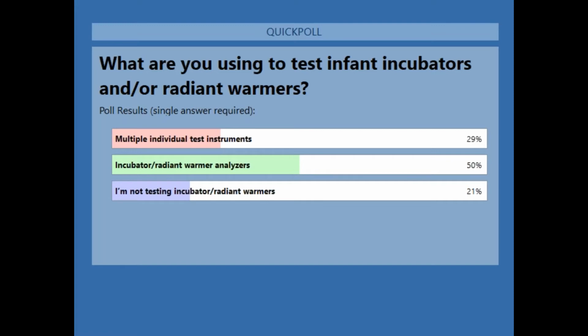Well, first of all, I think this is refreshing, because when we first introduced the original INCU, the number of people using multiple individual test instruments as a percentage of all respondents was much higher, as was the 'I'm not testing incubators or radiant warmers at all.' That was also higher. So to see that 50% of respondents indicate they're using some sort of infant incubator radiant warmer analyzer to perform their testing is really good, and it means you're getting reliable data that can be used.